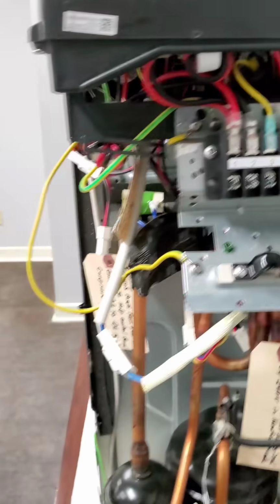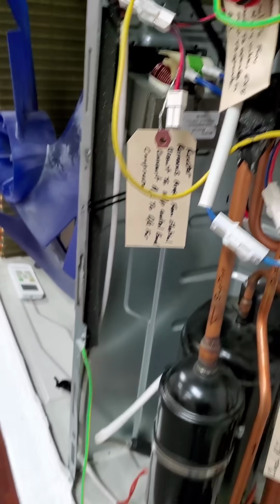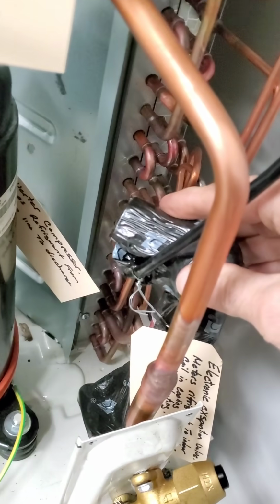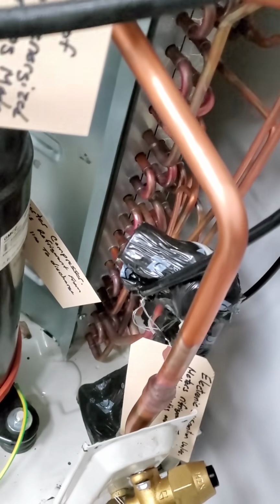So unplug your sensors. Let's see if we can get it right here. There's your main plug. If I can get it in there, zoom it in there, right there. So unplug your main plug for your sensors, and let's see if the E1 code goes away. Another thing that can happen is if you have an EXV valve right here. That is one plug. That EXV valve, let's see if I can find the plug. It's different on every one, but all you do is just follow your wire up, and right here it is. It's right beside the sensors.